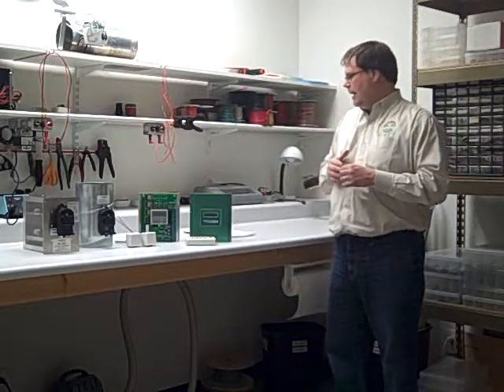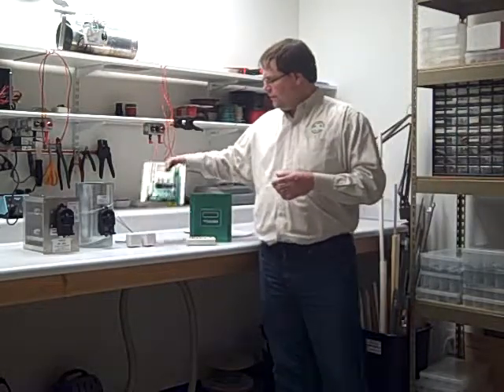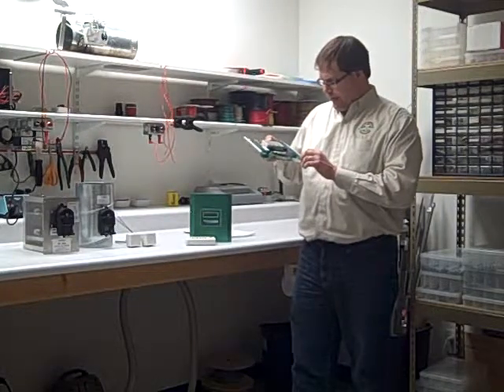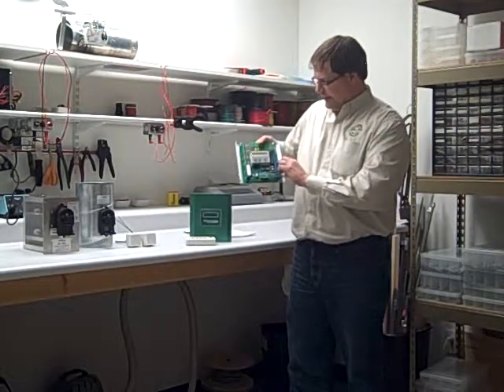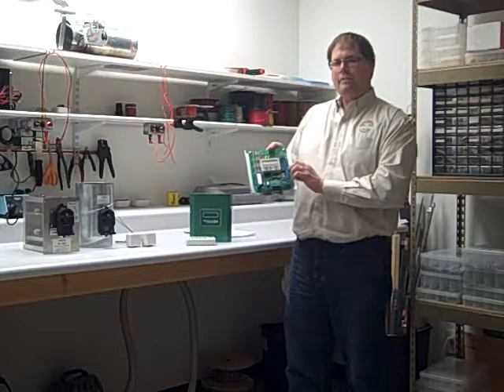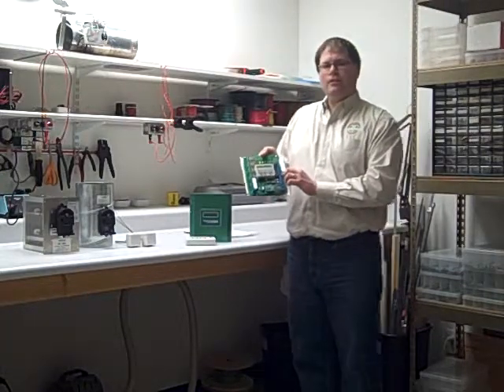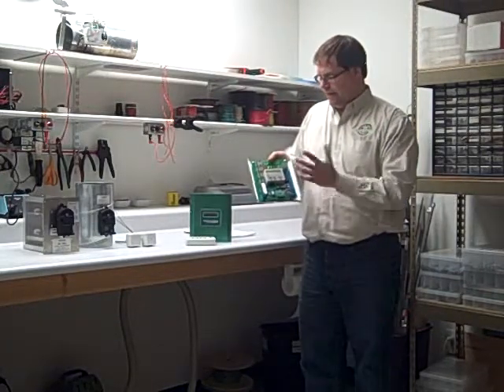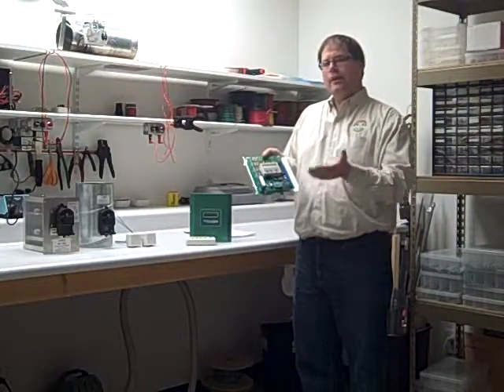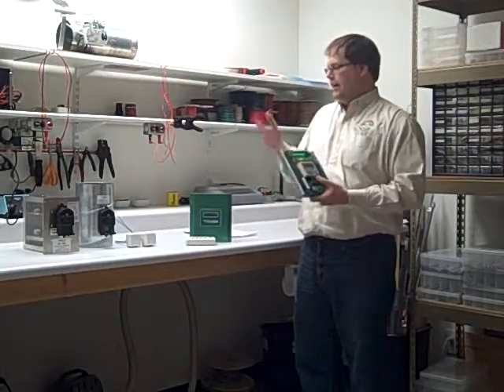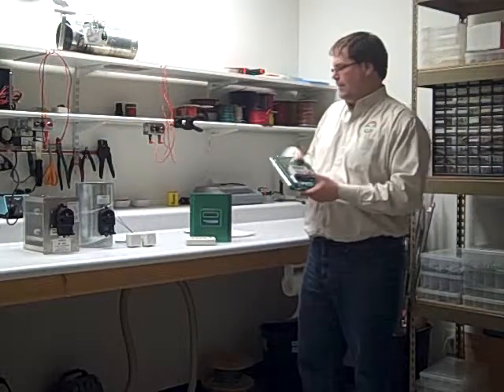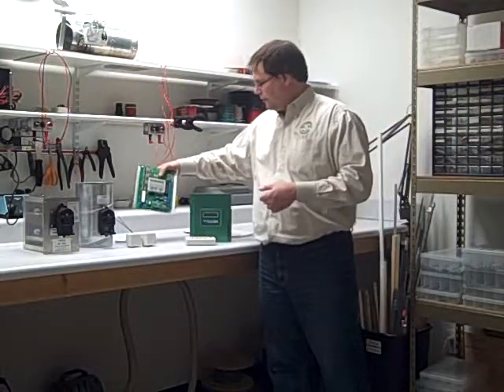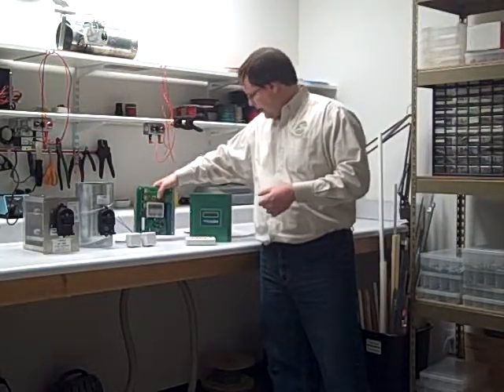Also, something we've added to this for the first time is what we call the DSBK terminal. Probably many of you have seen that. That allows you to control the fan and either the furnace or air handler to send it down to low speed to allow better control and better performance out of the equipment. So we're glad to add that this time.